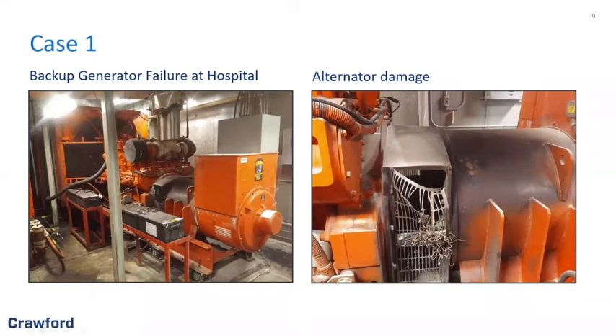As again, this unit has a mechanical portion and an electrical portion, i.e. the engine and alternator. We retained a mechanical and an electrical engineer to assist in determining the cause of loss and scope of repair. It was determined that the cause was an electrical failure within the alternator side over here, and there was no outside interference such as water, lightning, anything like that. So we had a pure equipment breakdown loss. No other policies were contributing.